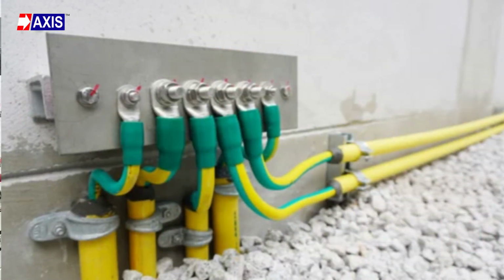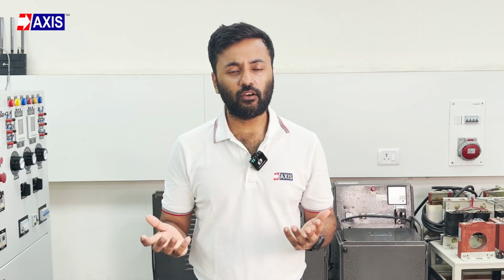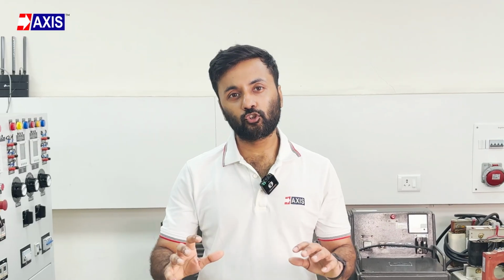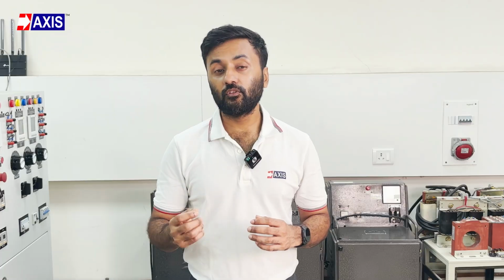In this case, you will likely see that metal parts like bus bars, cable trays, or clamps have shifted, bent, or become loose after a strike. This can happen inside panels, junction boxes, or internal electrical wiring. This sign means that a large amount of current has passed through the conductor, creating a strong magnetic force. This force can physically push or pull the metal, even though the strike lasted for only a few milliseconds.